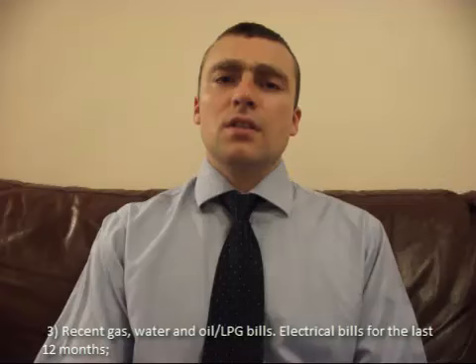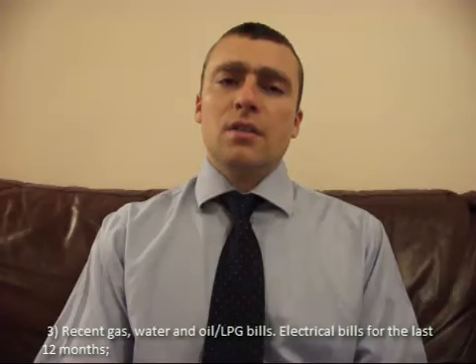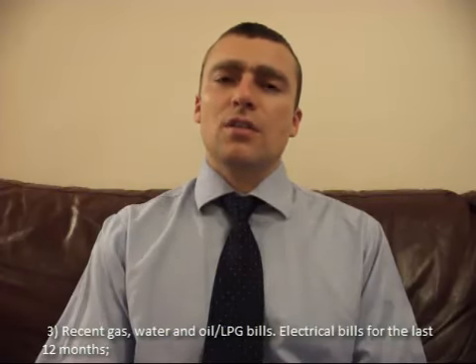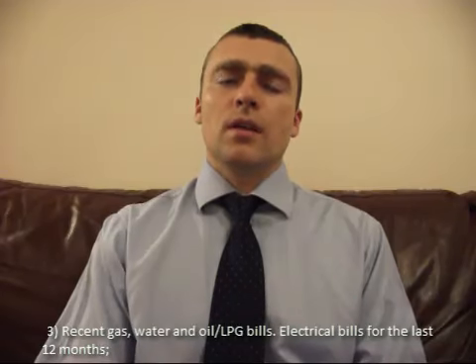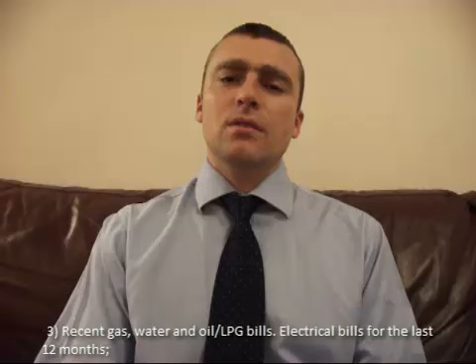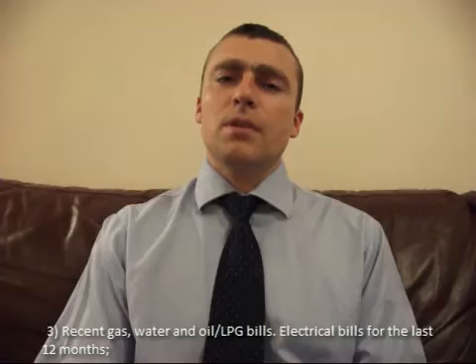In terms of electricity, you've got to supply at least for 1 year for every month. The reason that you need to have one for electricity is there is triad charges hidden in there, and the companies will have to see that there might be some other charges, like if you have power factor below, say 0.8, 0.9, you might be getting charges which you are not actually aware of. By supplying those bills, the companies will be able to assess how to make those savings for you.